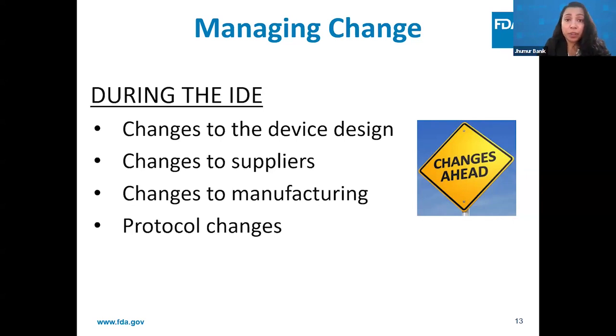And the other thing that, as a prior reviewer, I have seen is sometimes there's the use of various versions of the investigational device. So making sure you have good traceability in terms of, okay, this report was tested on this version of the investigational device, and this report was tested on this version, and rationale supporting the equivalency could help expedite that review. Though it's not advised that that's the approach to take, but in the event that it happens, those are things to consider.